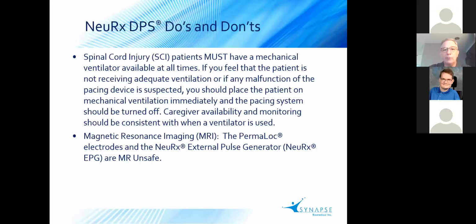Now to cover some of the do's and don'ts of diaphragm pacing, spinal cord injury patients must have a mechanical ventilator available at all times. If you feel that the patient is not receiving adequate ventilation or if any malfunction of the device is suspected, place the patient back on mechanical ventilation, or provide them a method of breathing. That could be an ambu bag. If they're using non-invasive ventilation, that could be that. But place them back on their breathing help and turn the pacing system off.